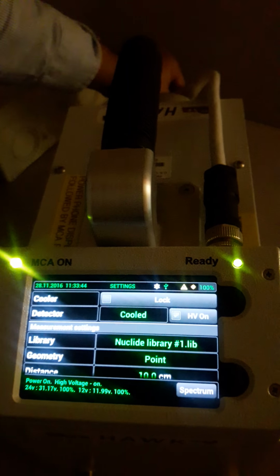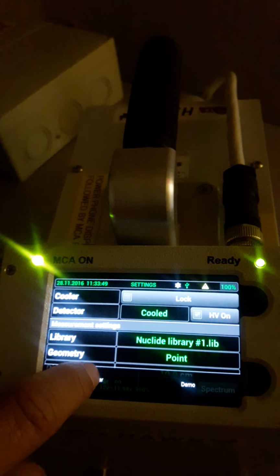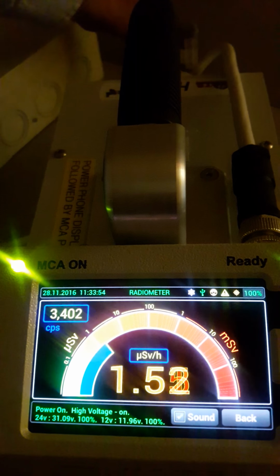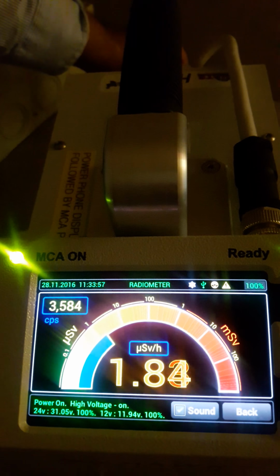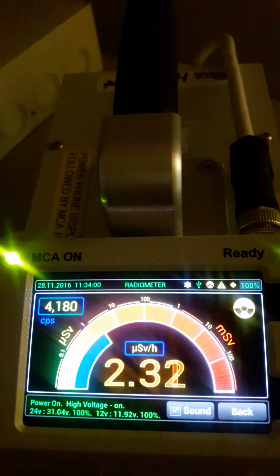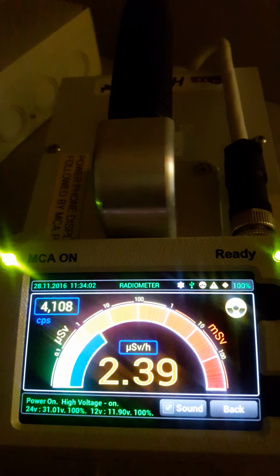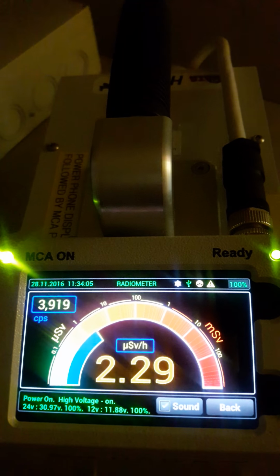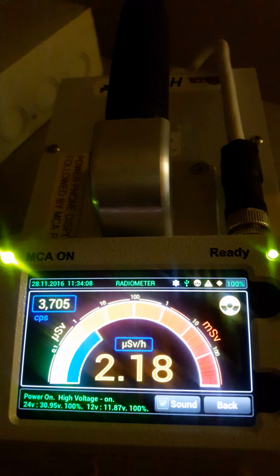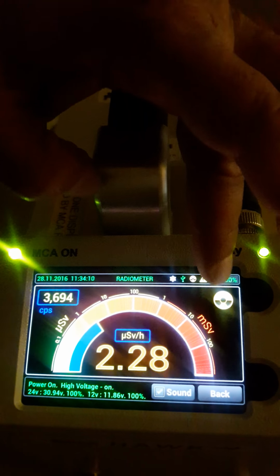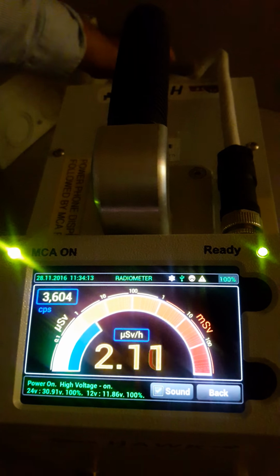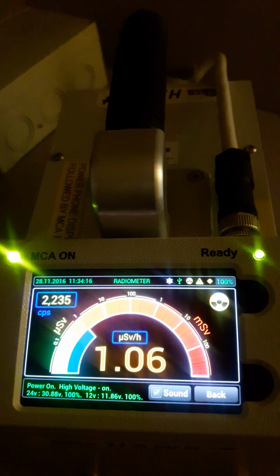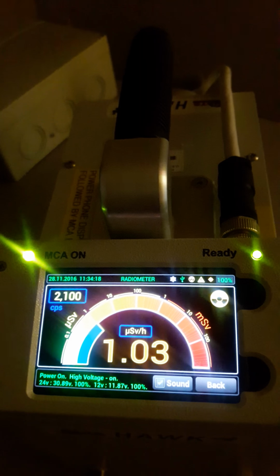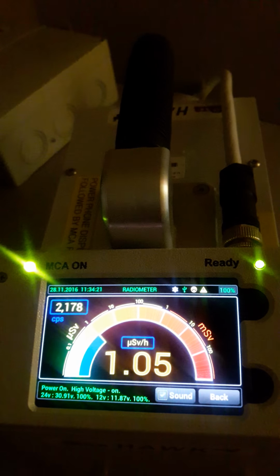First thing I'm going to do is go into this mode down here, and I'm going to select the radiometer mode. So you can see that in the radiometer mode, I'm detecting a source, and it's telling me that it's so many counts, and it's giving me the dose information in microsieverts per hour, and it's flashing in here. That's basically telling you that it's detecting a hot source. I have about a 5 microcurie cesium source, so it's fairly sensitive in here. So I know that I have a source in here.